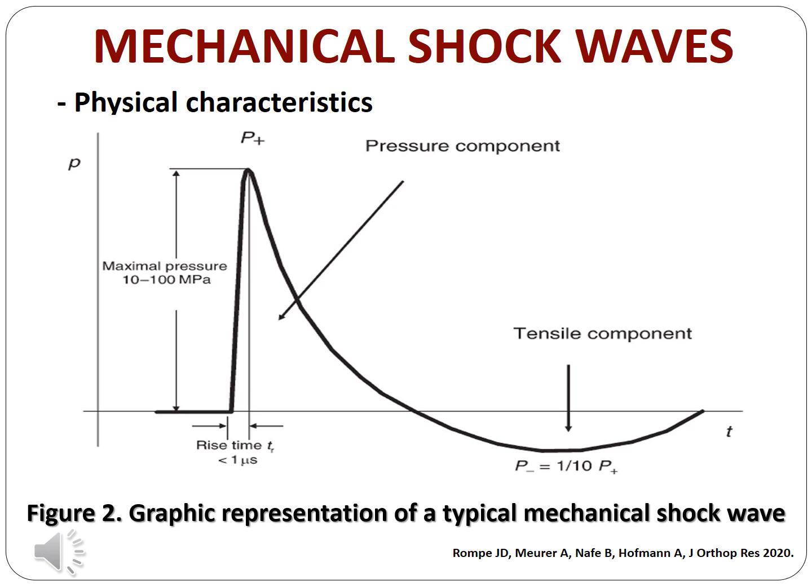Subsequently, radial shock wave devices were developed. They use compressed air or electromagnetic forces to launch a projectile located inside the device. The projectile achieves high speed, transferring its energy to the applicator, which is in contact with the skin. Depending on the energy they have, that is, depending on energy flux density, mechanical shock waves can be categorized as low energy, medium energy, and high energy mechanical shock waves.